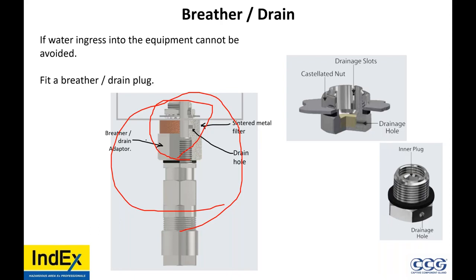Is sealing required to the cable gland used for an EXE enclosure, such as an instrument enclosure, class 1, zone 2? Well, if you want more than IP54 or a guarantee of IP54, yeah. Is sealing required for a pressure transmitter? Well, once again, if you buy an IP66 gland and an IP66 device, the only way you're going to get IP66 is install the O-ring or the IP washer, the sealing.